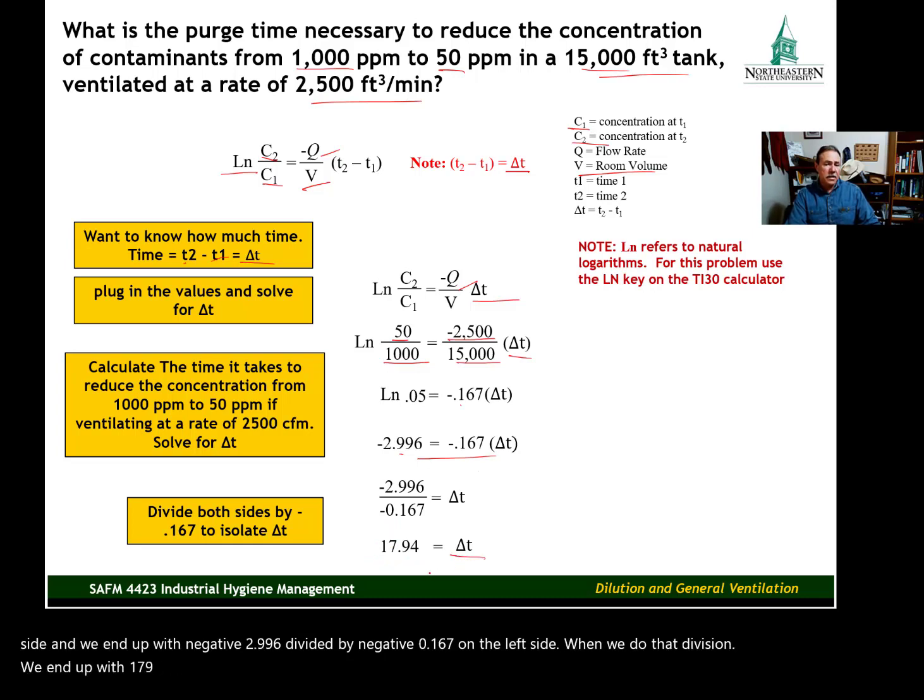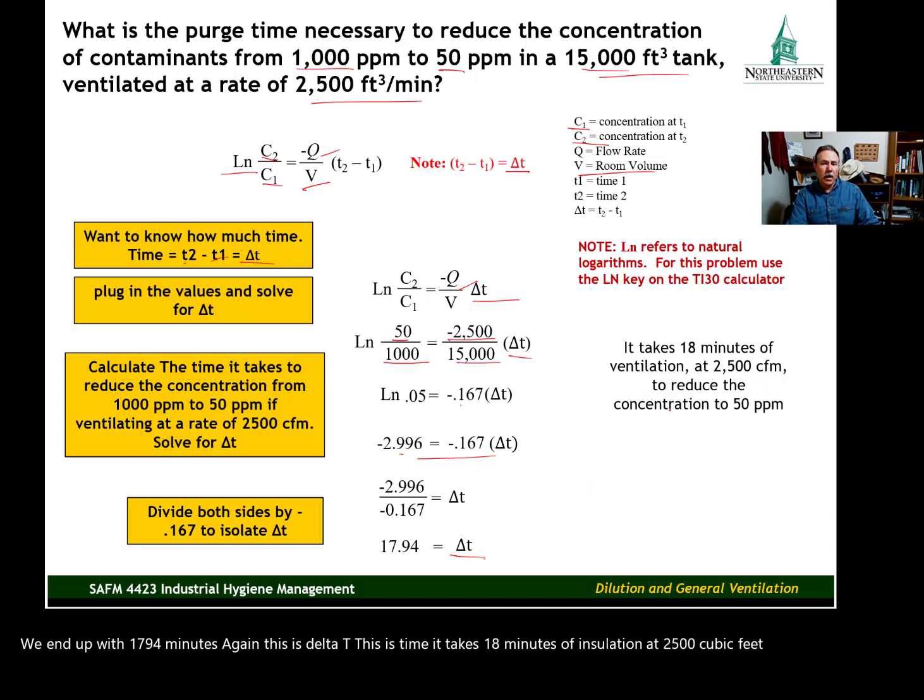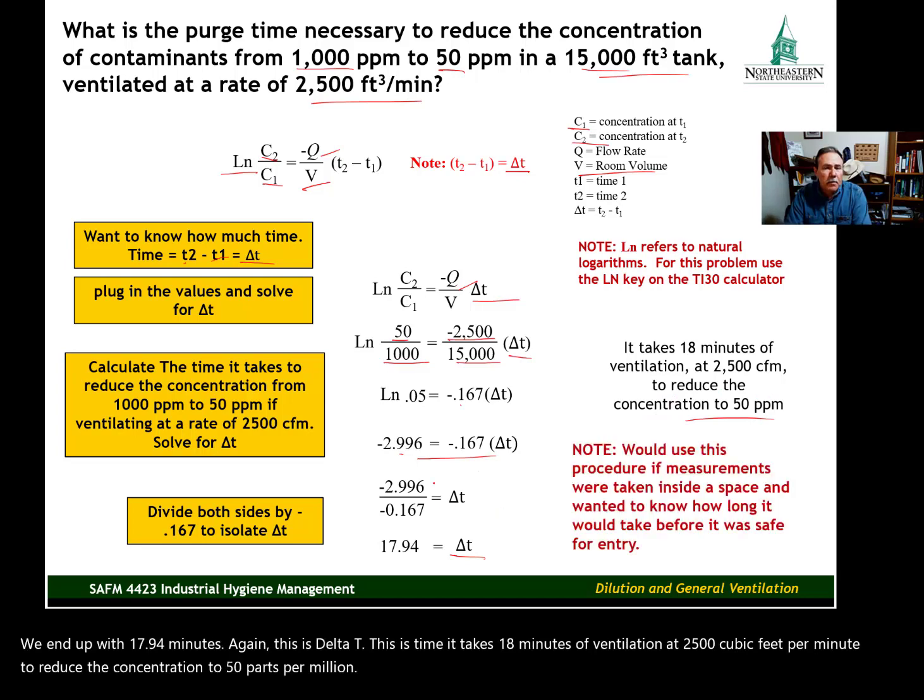Again, this is delta T. This is time. It takes 18 minutes of ventilation at 2,500 cubic feet per minute to reduce the concentration to 50 parts per million. If you have any questions, let me know and we'll get those questions answered. I'll see you in the next video.